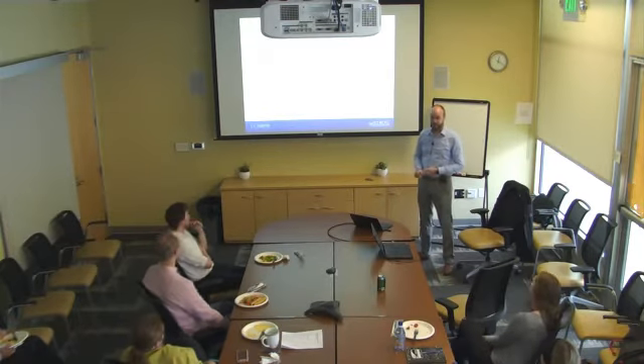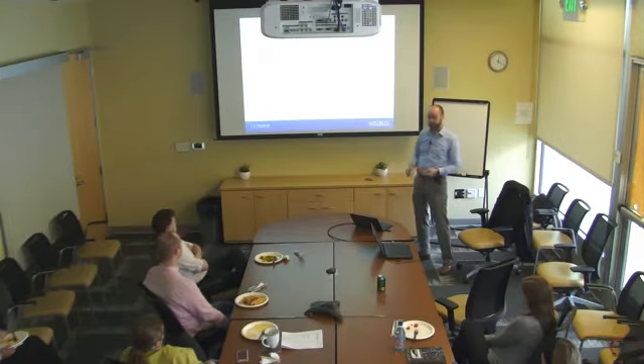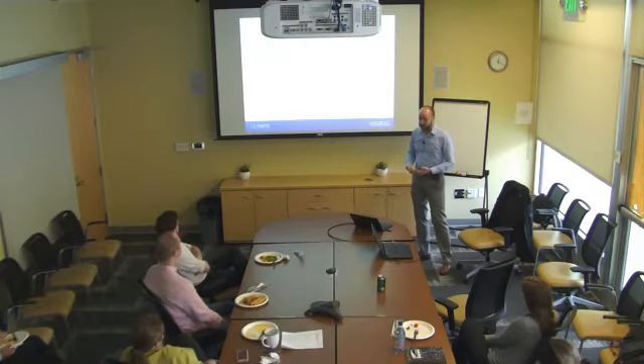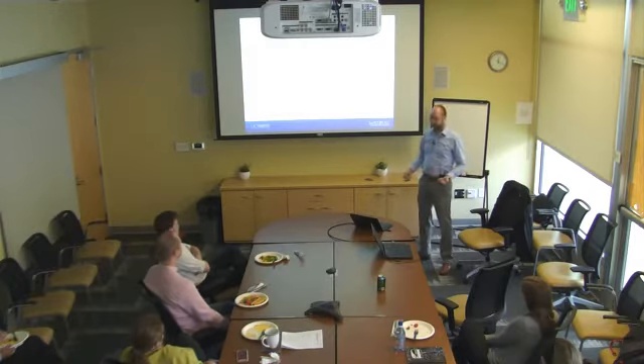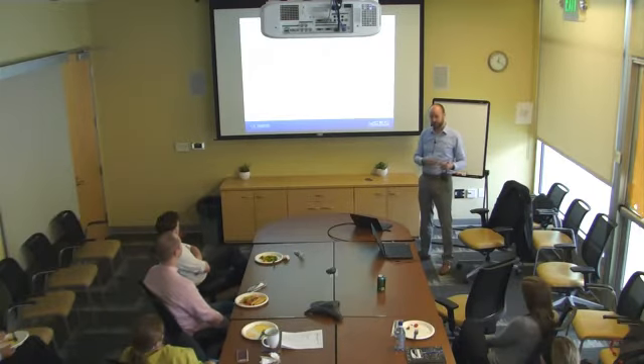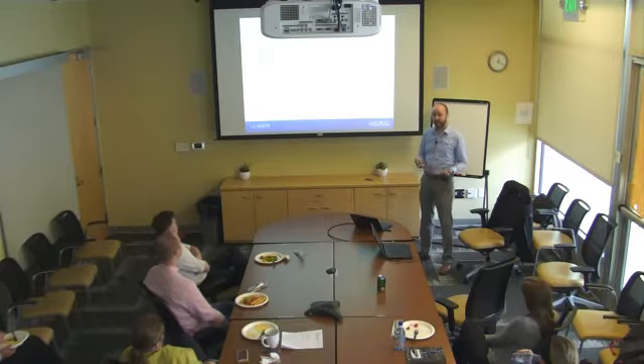So there were two things I modeled: demand response and the permanent load shift program. When I was modeling demand response, I picked the 12 hottest 4-hour segments of a day out of the year and said, okay, those are going to be my event days that I'm simulating. Then I used the 10-day average baseline that I described before and applied it to those days to figure out what their baseline would be for that time.